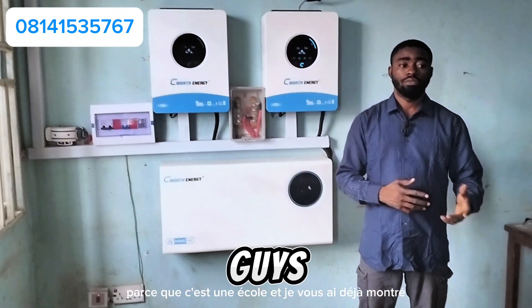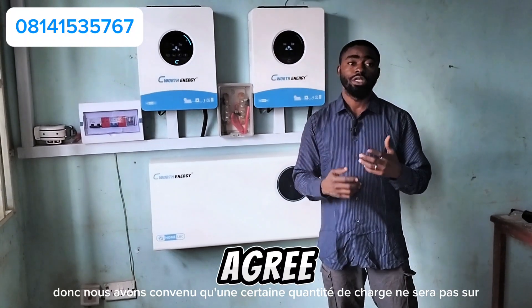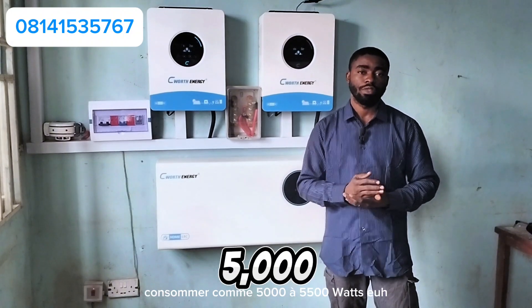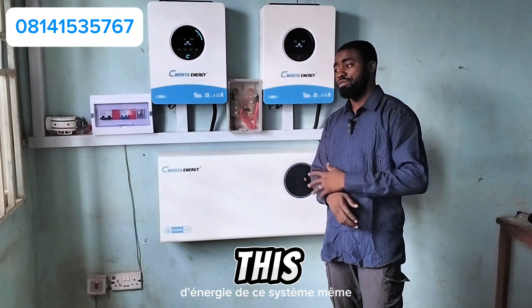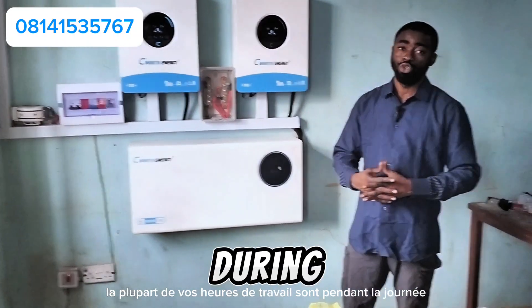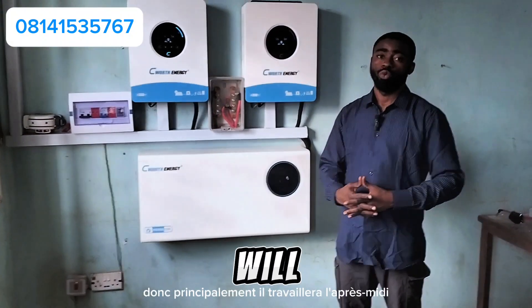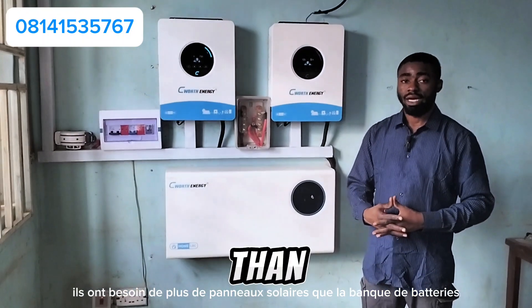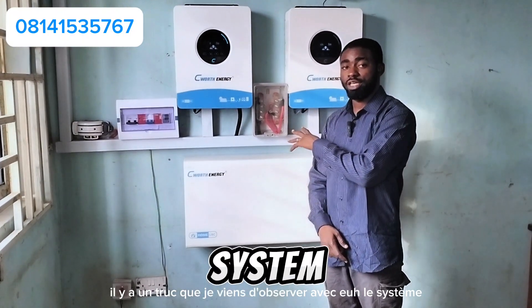The major working hours for this system will be from 8 a.m. to 5 p.m., because it's a school — essentially an office environment. We agreed that some loads will not be on at the same time, so at maximum they'll be consuming about 5,000 to 5,500 watts. Because most working hours are during the day, the system will be resting at night, which is why they need more solar panels than battery bank.